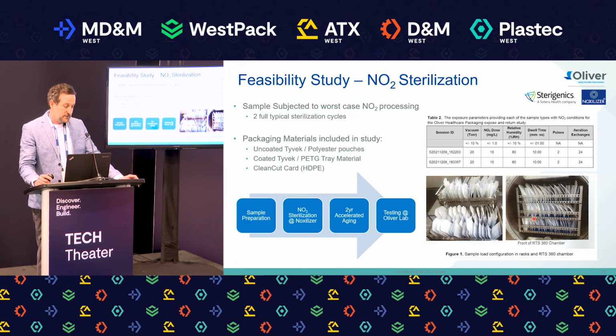So here's our study where we started. We subjected samples to worst case NO2 sterilization. So you may ask yourself, what's worst case? In this case, we took 2 full sterilization cycles from Noxilizer, and over here in this table on your right, this has the parameters of that study, and this is a one-time cycle. So we did 2 of those, and then subjected the packaging materials in this list to those 2 cycles.